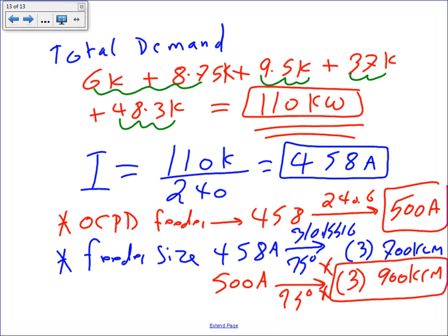Any question, my friends? I don't want to size the neutral, but in reality, you can take the 700, the 500 here, cut it by 0.7, and size the neutral. Remember, not all of them, no. For ranges only, you can cut everything that we did by 0.7 and calculate the neutral. To not complicate things, I pulled a full neutral.